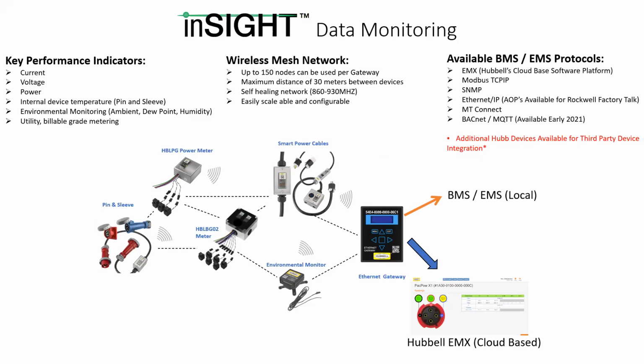Any type of Modbus, TCP/IP, SNMP. For Ethernet IP, we have add-on profiles that work with Rockwell Factory Talk. We worked with Rockwell directly to develop those, so there's no additional devices needed. You could add any one of our devices to their system and use it with their software. We just recently did an update where now the gateways are fully compatible with their stuff up to 150 nodes. Originally, the gateways had a bit of a limited amount due to communication timeframes.